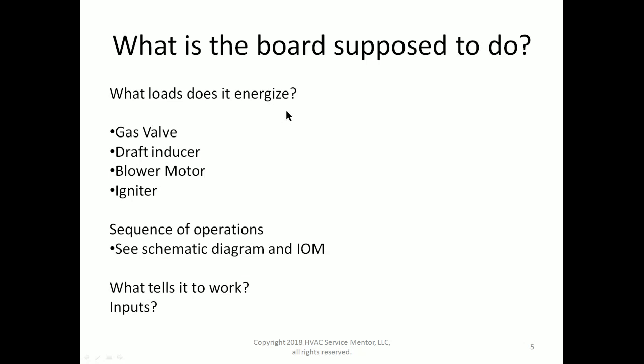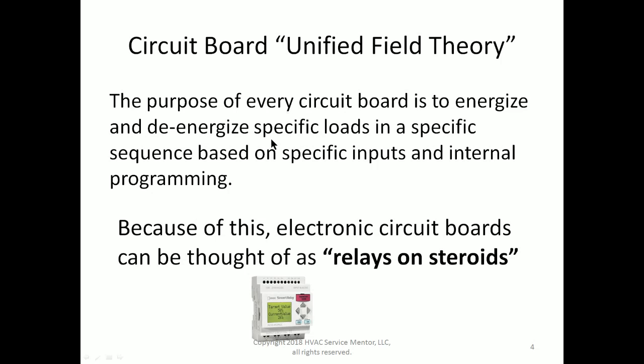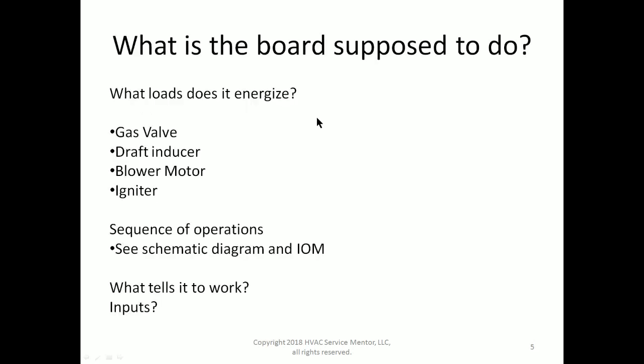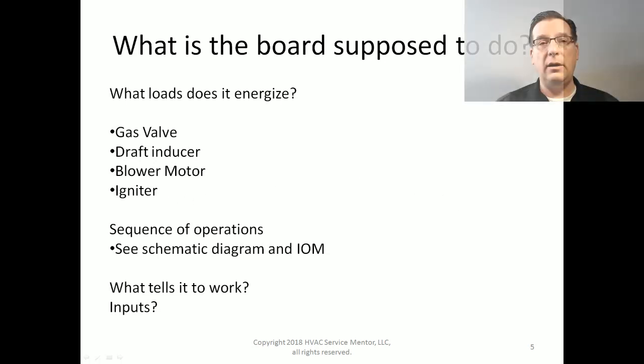And let's start with the loads, because remember, every electronic circuit board's job is to energize and de-energize specific loads. So if we can figure out what loads it energizes, that's going to take us a long way down the road to identifying what it's supposed to do. So for example, an integrated furnace control board is supposed to energize a gas valve. It's supposed to energize a draft inducer motor. It's supposed to energize a blower motor. And it's supposed to energize an igniter. Cool. That simplifies things quite a bit.